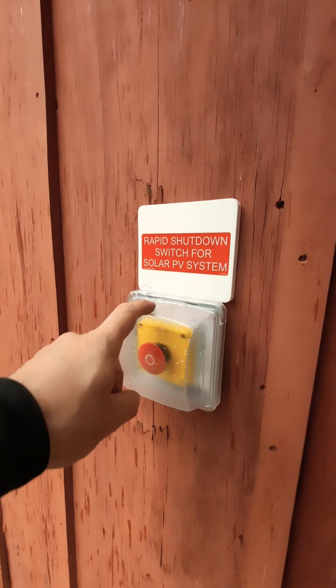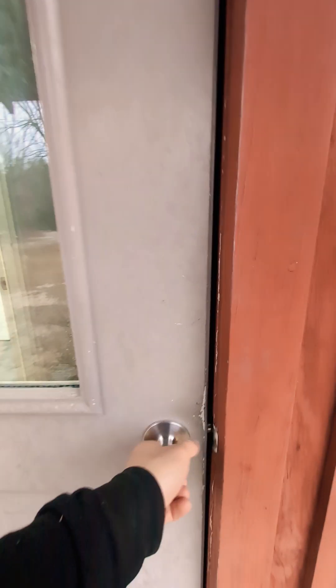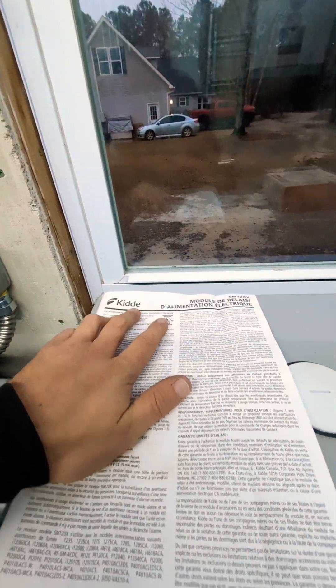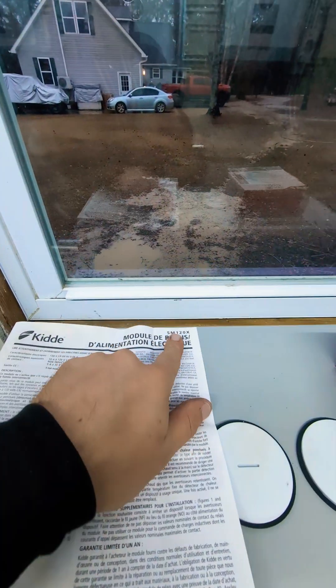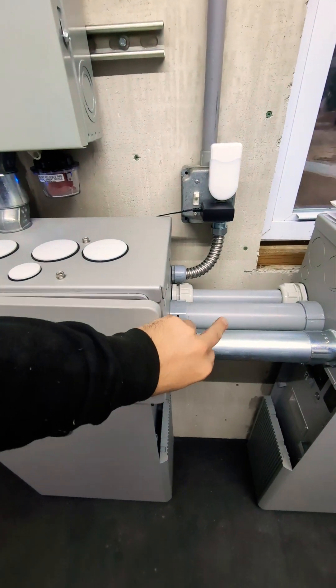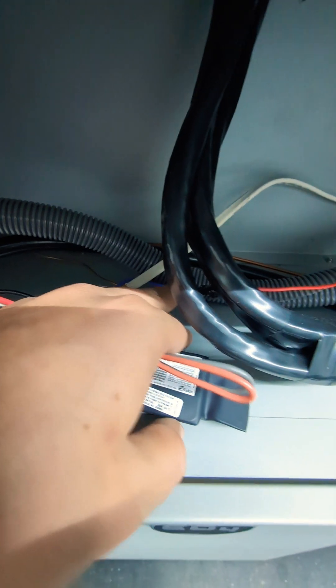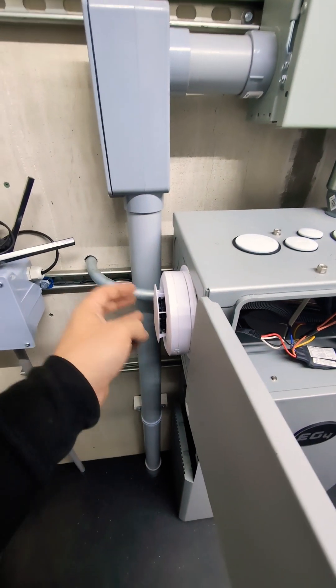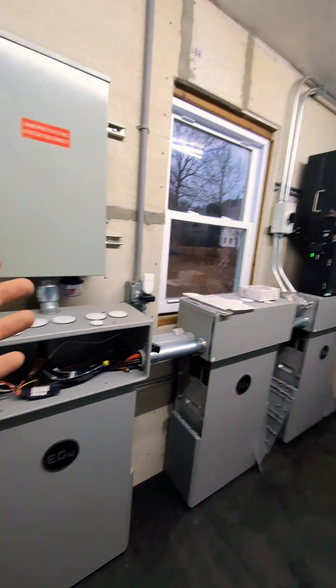RSD, or rapid shutdown, is a requirement for all solar arrays on buildings which are not open structures. I have included with my rapid shutdown these Kidde alarms that also work with this SM120X relay device, which is now spliced in line with one leg of the rapid shutdown wire. So if this alarm goes off, it will also trigger the rapid shutdown.